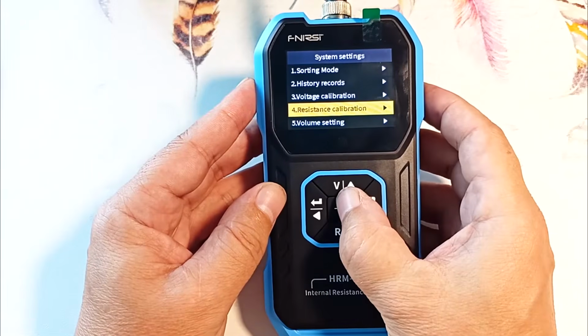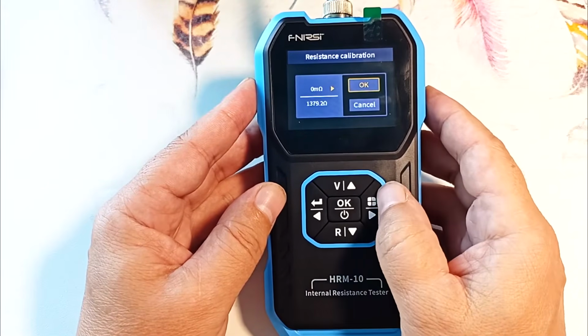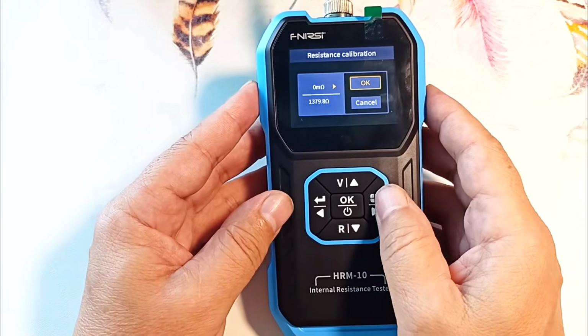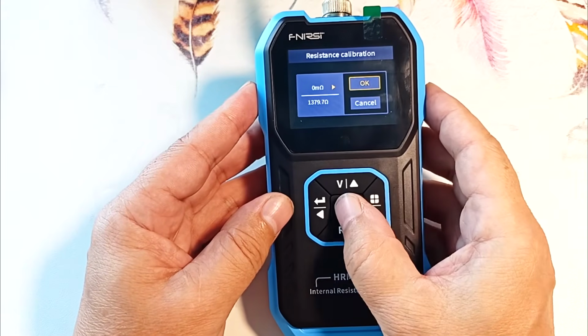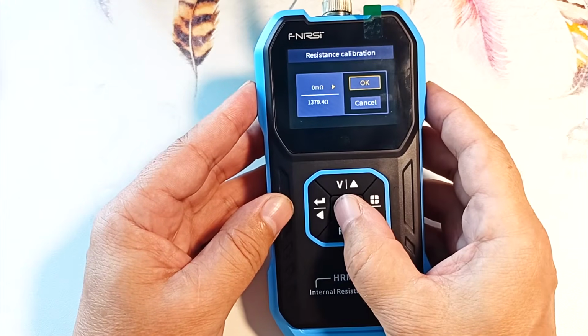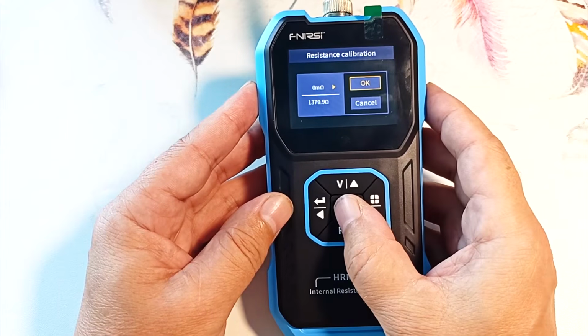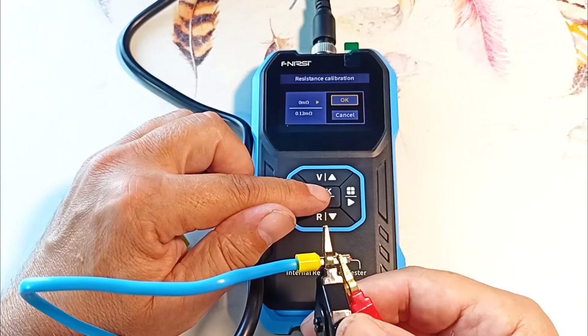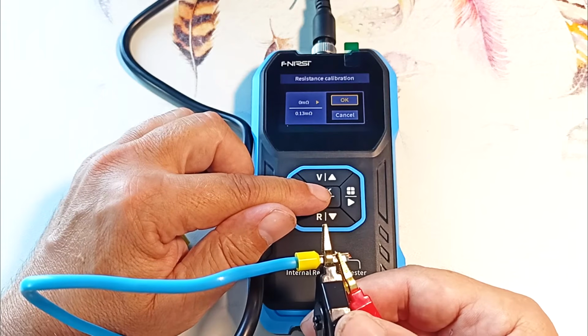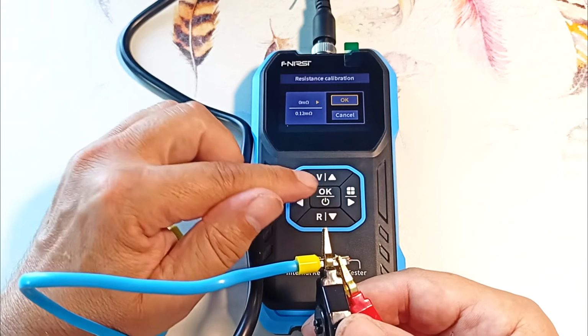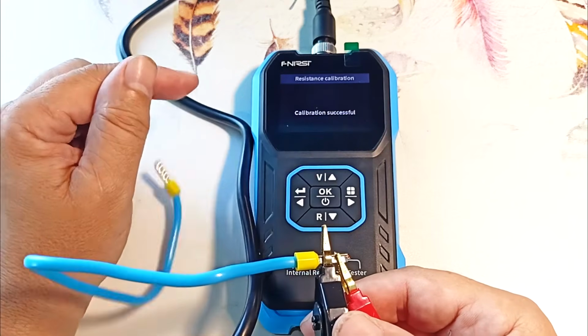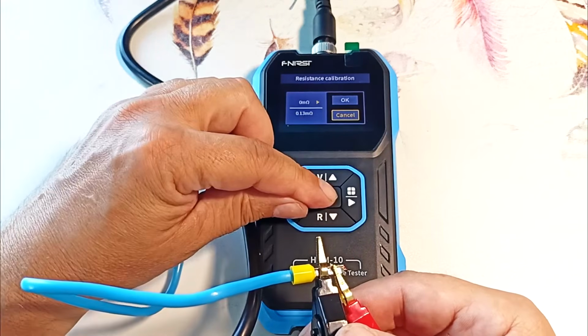The next point is resistance calibration. Here too, standard resistances are needed for calibration. I don't have any - the only thing I can do is calibrate the zero, and there's no need to hook the probes to each other. We take a conductor and place the probes as close to each other as possible. Click OK - zero is calibrated.